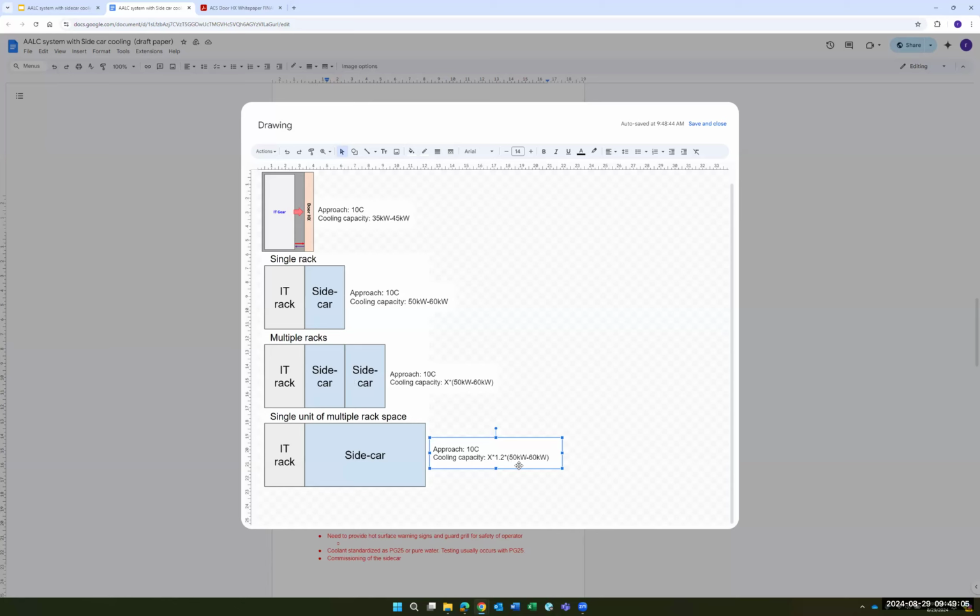Yep, and you're also getting better airflow because the airflow is straighter through the wider cabinet than it is through the narrower cabinet. Yes. So you have multiple efficiency features in this. Now you can use bigger fans than whatever you are using in this. So there are multiple advantages. That's why I think 1.2 is a good justification for this.